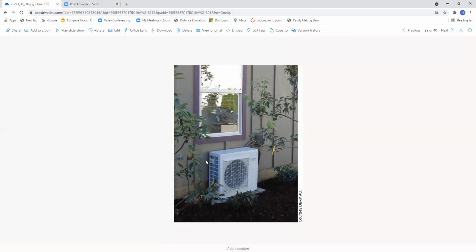But what am I saying? Read the manufacturer's service and installation instructions. They will give you a recommendation for how far this unit is to be from a wall. Luckily, this is a horizontal blade design, so you're pulling air from the back and discharging out through the front. That being said, we still need that airspace in order for this thing to be truly efficient.